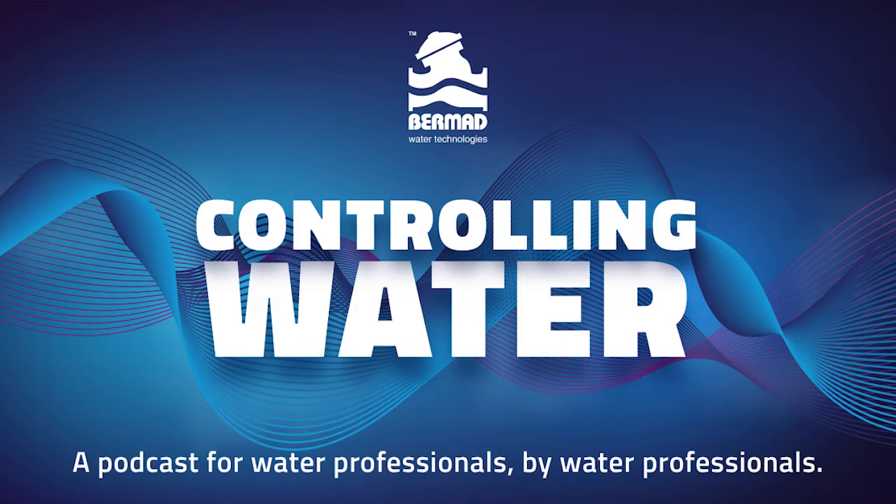What sort of accuracy can someone expect compared to a mechanical water meter? Yes, they're definitely accurate and it's one of the key reasons why someone will want to put one in. A typical mechanical water meter operating within its nominal flow range would normally be plus or minus two percent up to a maximum of plus or minus five percent. If you're using any form of meter for billing, the more accurate it is the better, and a mag flow meter typically is going to be accurate within 0.2 to 0.4 of a percent.